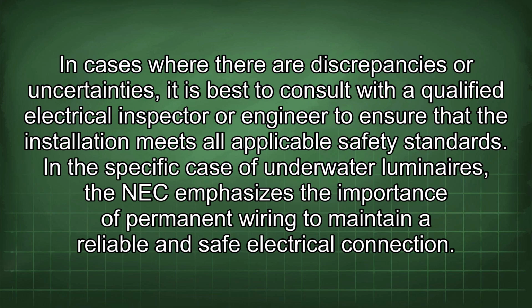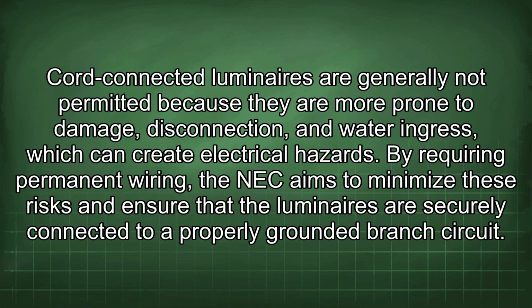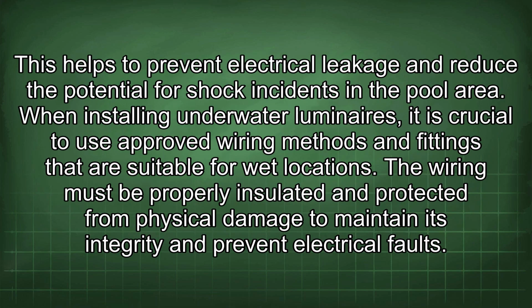In the specific case of underwater luminaires, the NEC emphasizes the importance of permanent wiring to maintain a reliable and safe electrical connection. Cord-connected luminaires are generally not permitted because they are more prone to damage, disconnection, and water ingress, which can create electrical hazards. By requiring permanent wiring, the NEC aims to minimize these risks and ensure that the luminaires are securely connected to a properly grounded branch circuit. This helps to prevent electrical leakage and reduce the potential for shock incidents in the pool area.